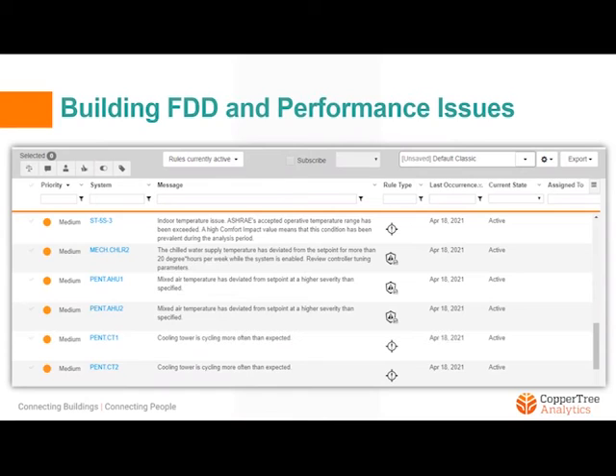And from here, the user should be able to say, well, indoor temperature issue, my temperature is outside of ASHRAE's temperature range. I want to assign this to operator A. And then operator A gets an email, let's say, when they are alerted about it, or when they log into the system, they should have it under their tasks list. They should be able to take a look at all of the trends and the recommendations coming from the analytics platform, start acting on that issue, change the status from open to in progress to closed eventually, add comments so that next time something similar happens, it may be a different operator or a different user looking at that issue, and they have all of that action summary.